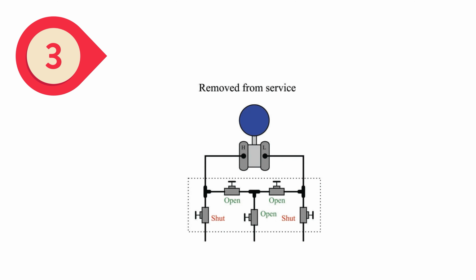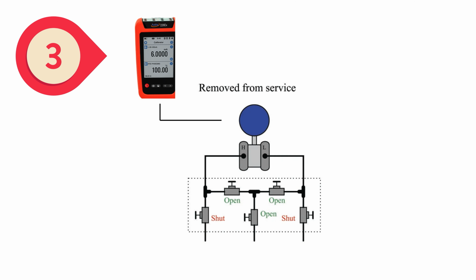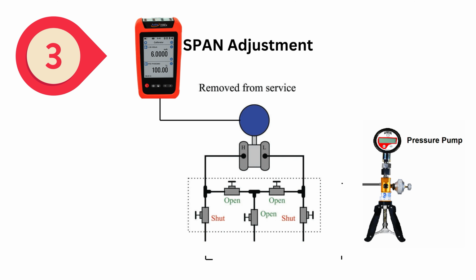Step 3. Span adjustment. Apply a known reference value that corresponds to the maximum range of the transmitter. For example, if it's a pressure transmitter, apply full-scale pressure. Again, access the transmitter's adjustment mode. Adjust the span setting so that the transmitter's output matches the reference value.